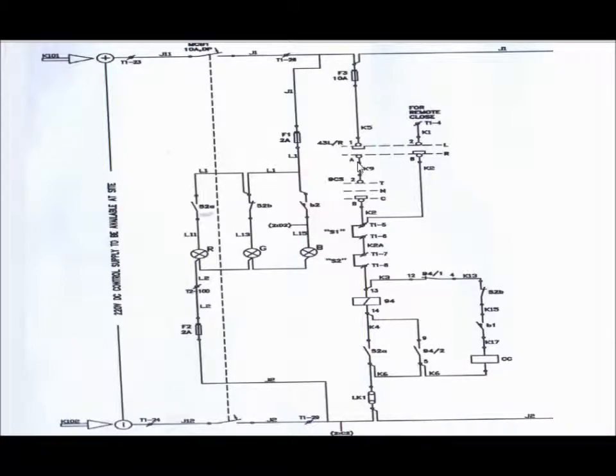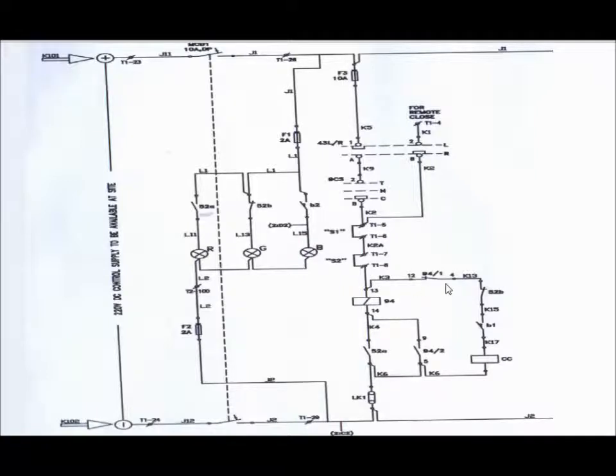Now if the local-remote selector switch remains in local position and we give the closing pulse from the control switch, the DC positive will come through the local-remote selector switch contact, to the control switch, to the auxiliary contact 94/1, to the auxiliary contact of 52B, and through the spring charge auxiliary contact to the closing coil. As soon as the closing coil energizes, the circuit breaker will be ON.